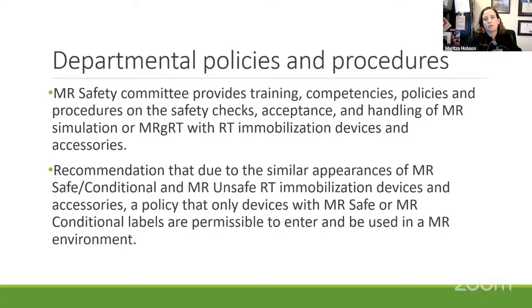And we also recommend that due to the similar appearance of MR safe or conditional and MR unsafe RT immobilization devices and accessories, a policy that only devices with MR safe or MR conditional labels are permissible to enter and be used in an MR environment. So this can be considered a restrictive and expensive recommendation. However, this is one of the failure modes that can be seen in that slide that I'll show you, where an MR unsafe stretcher was brought in because it looked like an MR conditional stretcher. So you don't want that to happen.